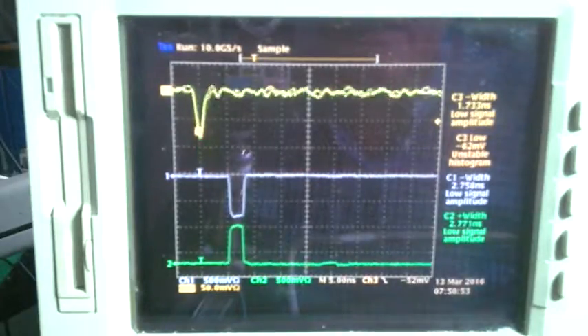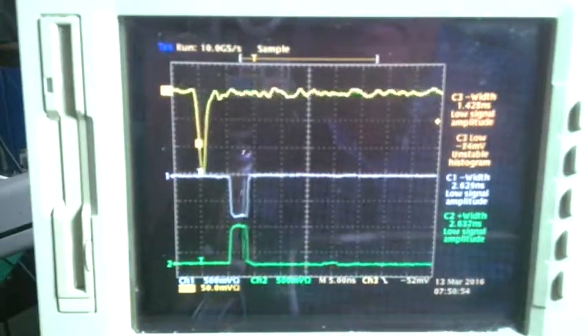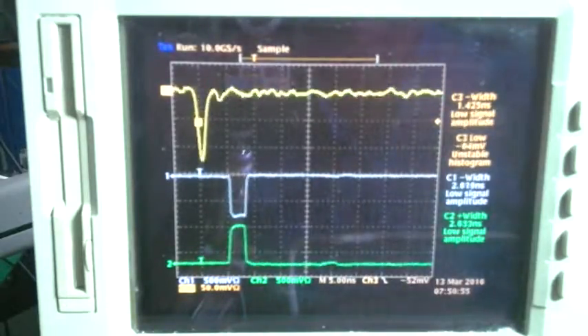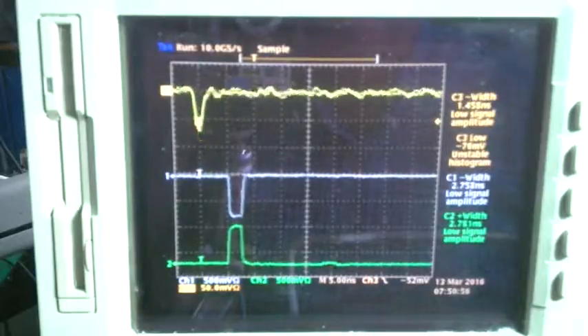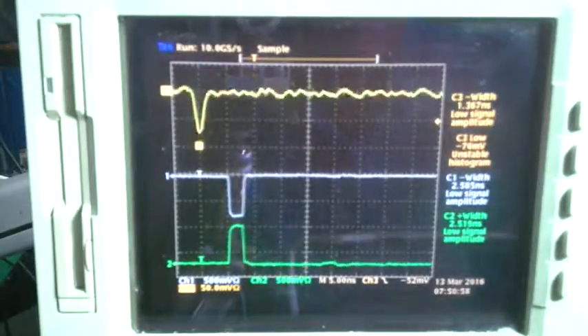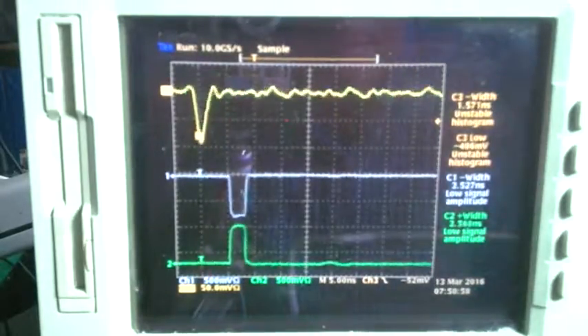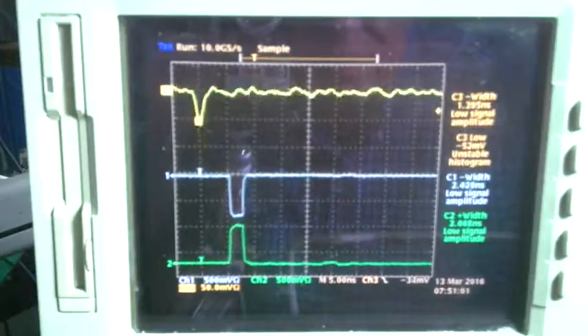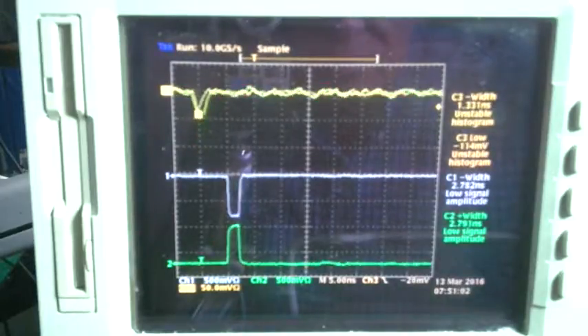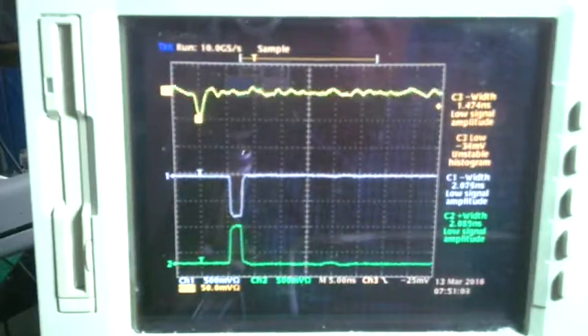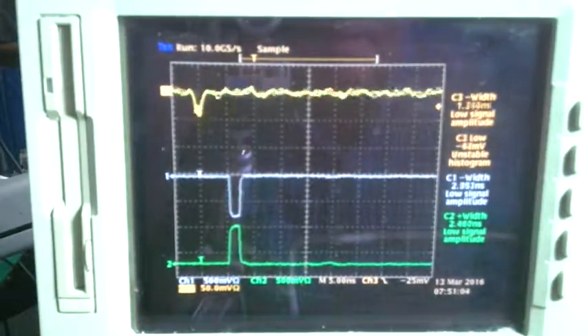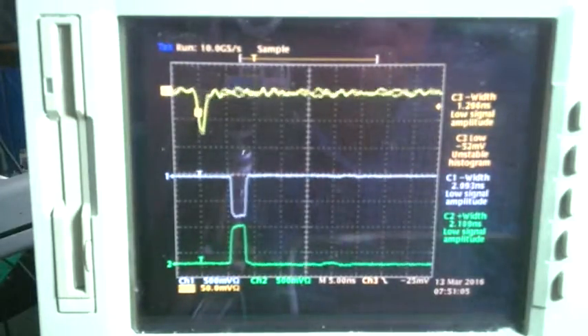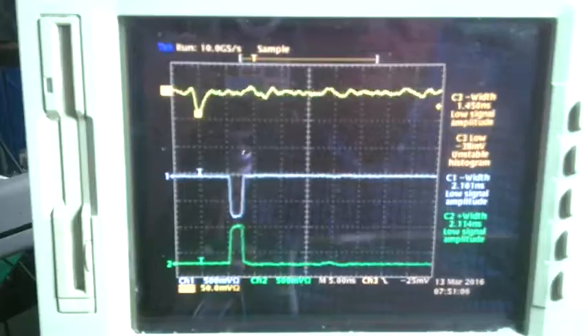Once again, you can see the variable pulse height from the photomultiplier. The threshold is at 52 millivolts negative. Go down to 25 and you see a much higher count rate.